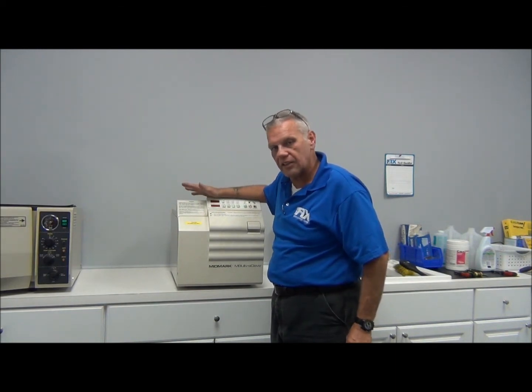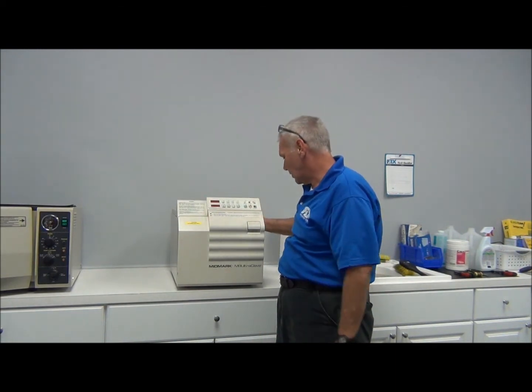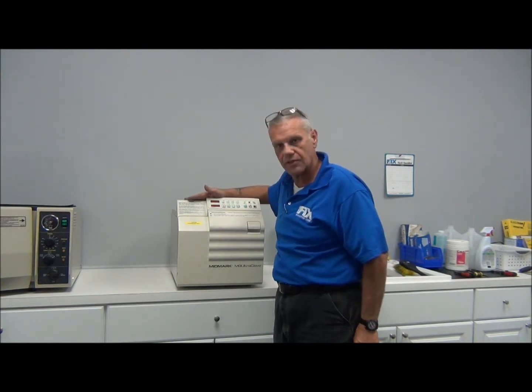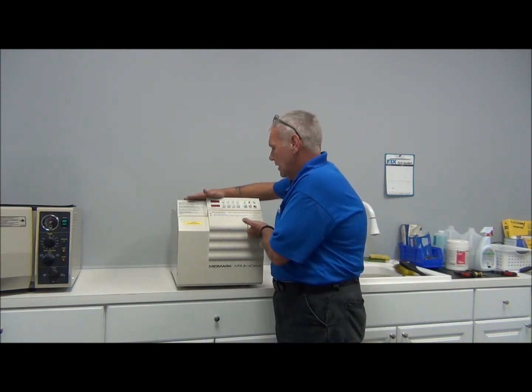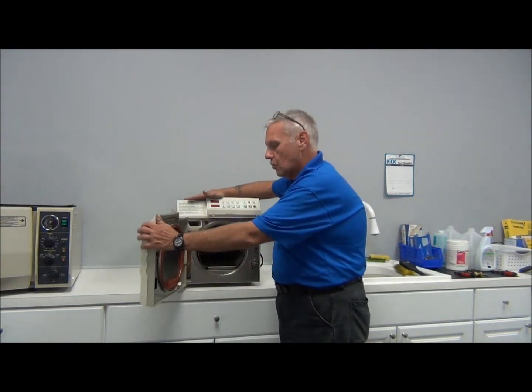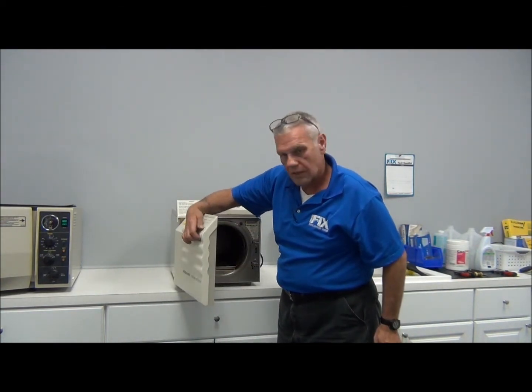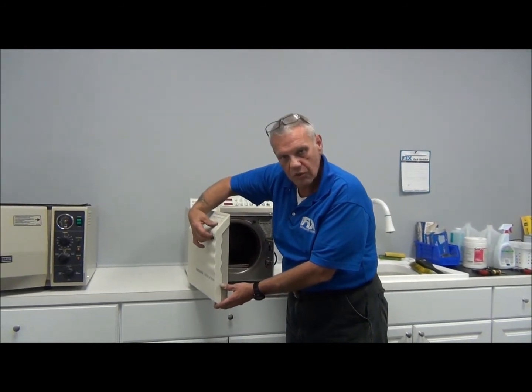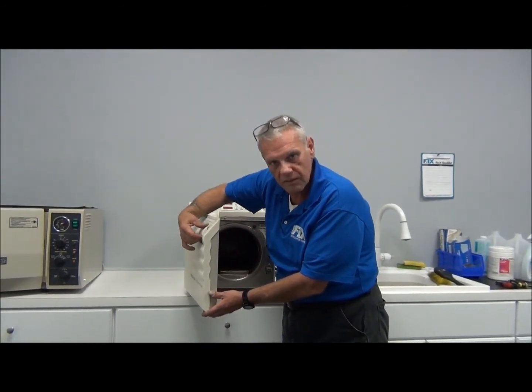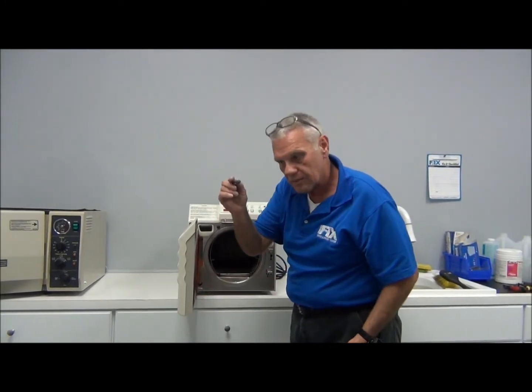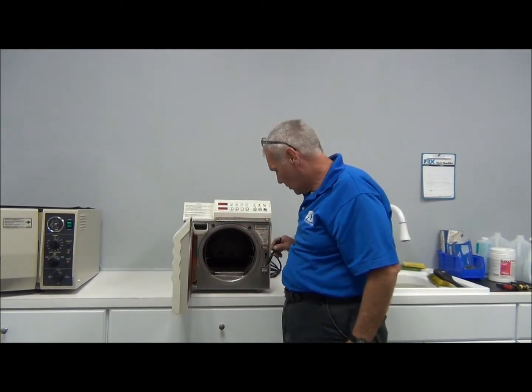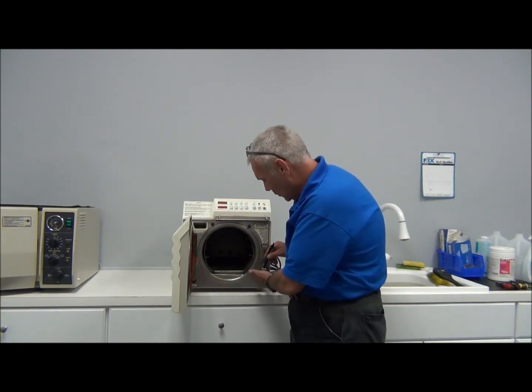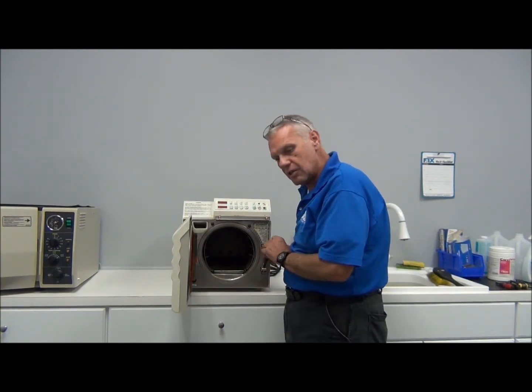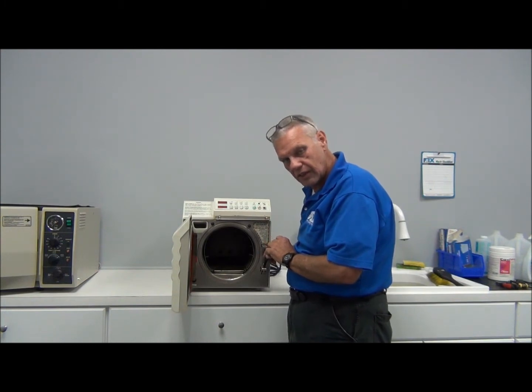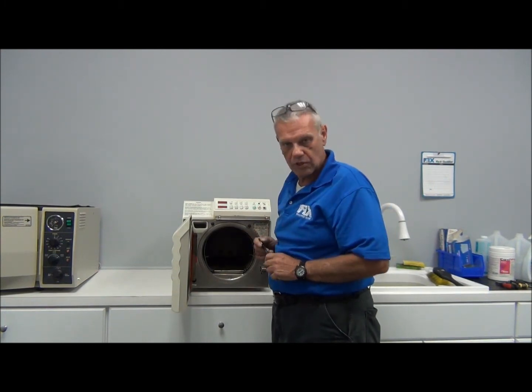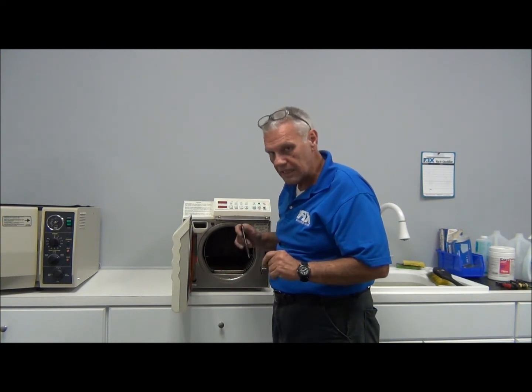rust, anything that could extenuate any circumstances, and we look pretty good, bearing in mind this is a 14-year-old sterilizer. It's in very good shape. Our next step is to open the door, manipulate the door latch, make sure it moves freely. Okay. Take something non-conductive, your pen or screwdriver, stick into the bottom rung of the door latch and make sure that we have a positive click that ensures us that the door switch is working. Bear in mind this is a PM and not a repair.